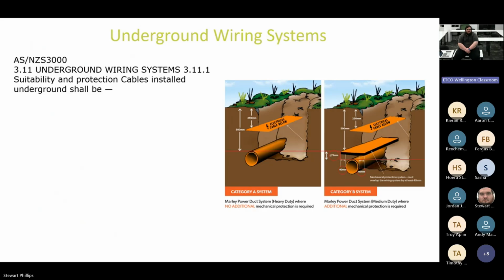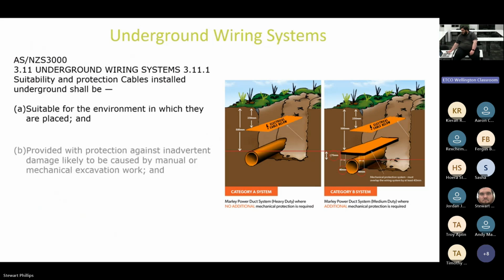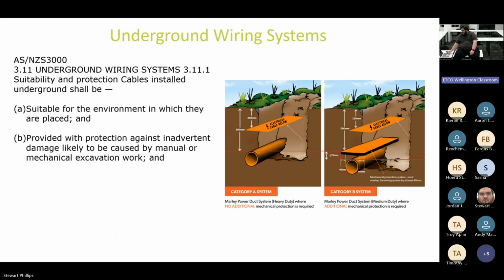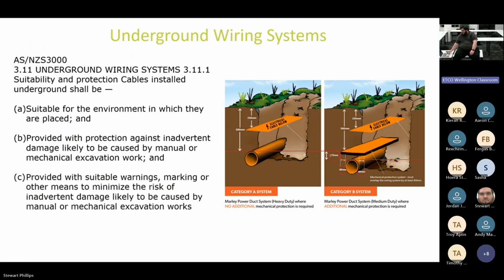So category A, Marley power duct system, where no additional mechanical protection is required. Then the Marley power duct system, medium duty, where additional mechanical protection is required. So you've got heavy duty versus medium duty. Cool. So suitable protection: cables installed shall be suitable for the environment, provided with protection against inadvertent damage, and provided with suitable warnings, markings, or other means to minimize risk.